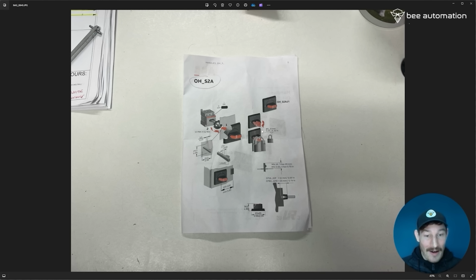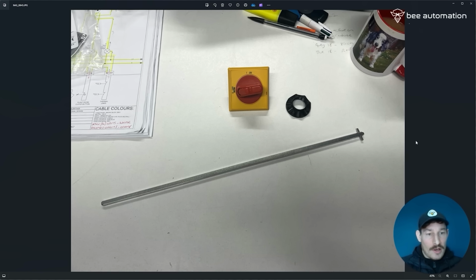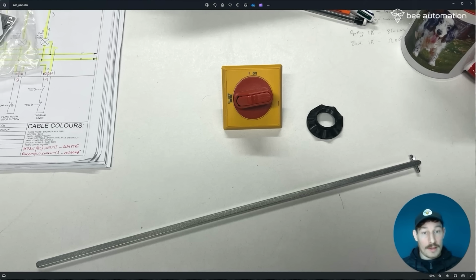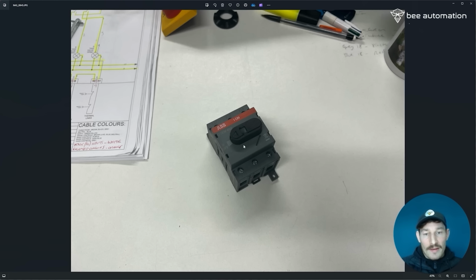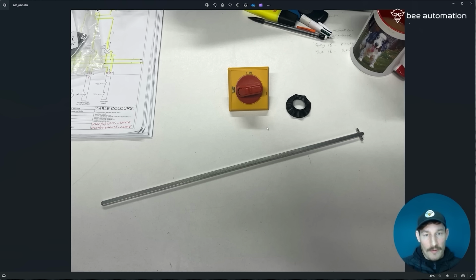I've read the manual and it gives you the measurements. This is the shaft I was using and the switch. To comply with BSEN 60204, you want to make sure that when the panel is on and live, if there's no other door catches or locks locked, you can't open the door - when you switch it on, it locks the door into the switch so you can't open it when live. This main switch I'm using is from ABB.